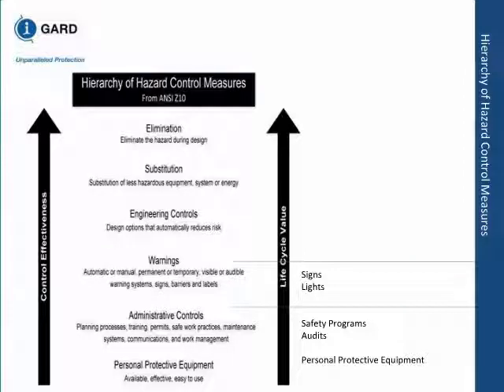Personal protective equipment is the least desirable. Personal protective equipment as it exists now only protects you against two hazards: thermal flash hazard and shock hazard. It doesn't have any protection against blast. Blast pressure can literally blow you away. You do not have any protection against shrapnel coming in. Personal protective equipment can be penetrated.